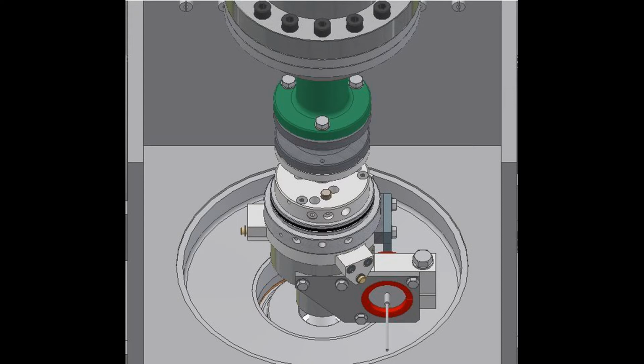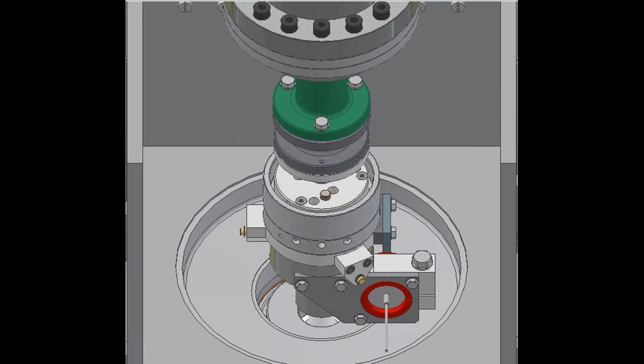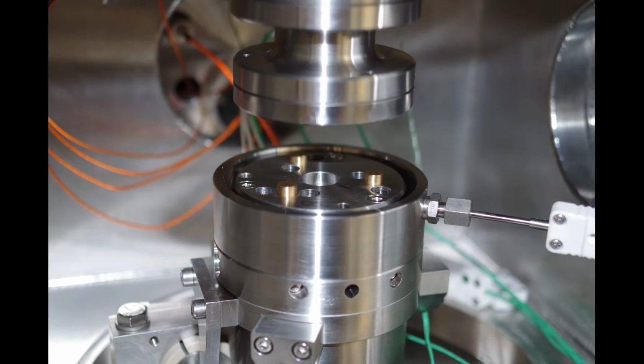Connect the thermocouple to socket 1. Make sure the tip of the thermocouple is pressed against the side of the pin mounting plate. If lubricated tests are to be performed, fit the fluid bath tube wall and add lubricant as required. The machine is now ready to run a pin-on-disc test.